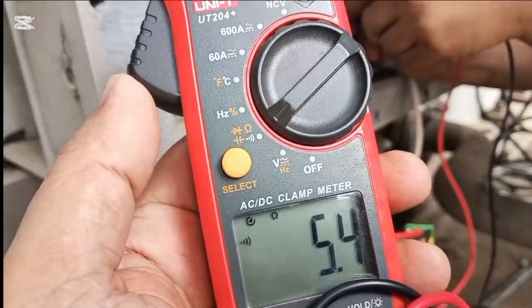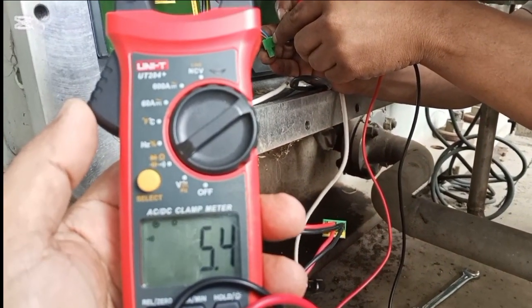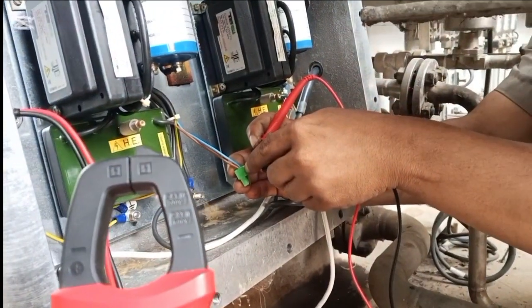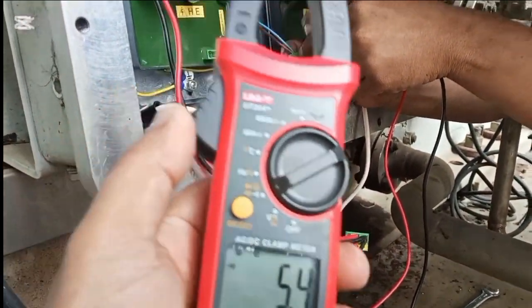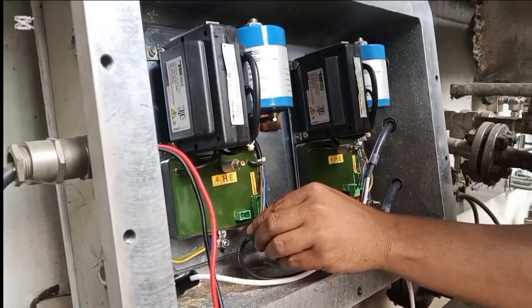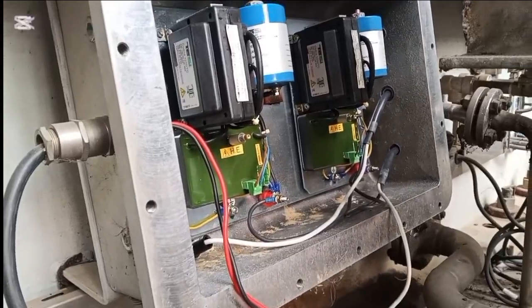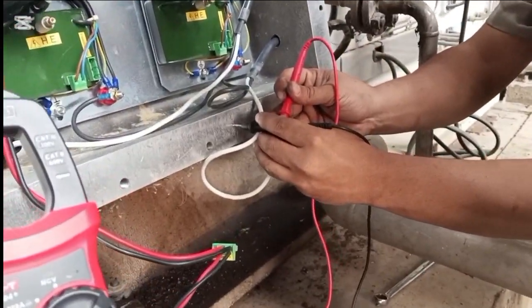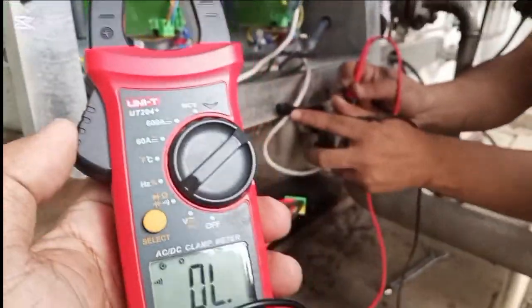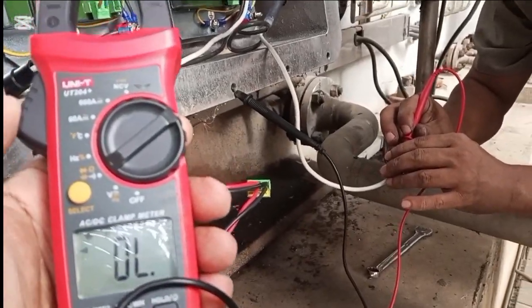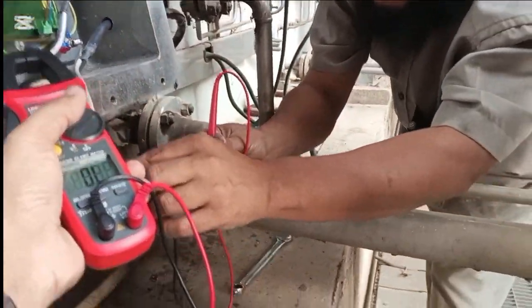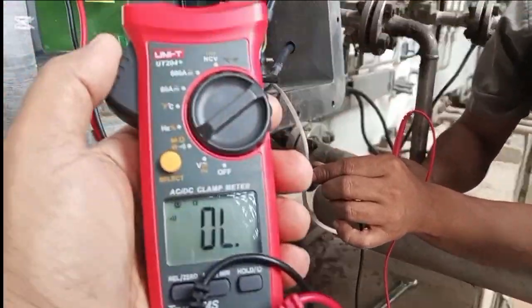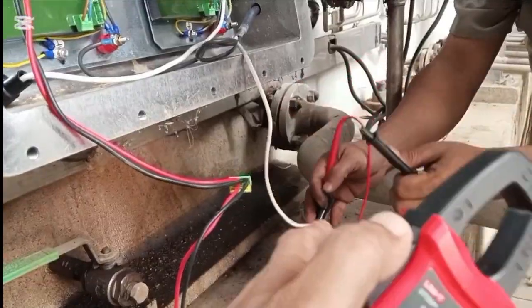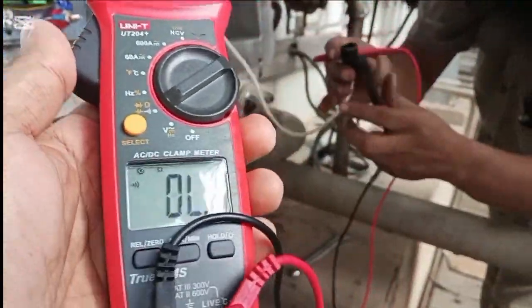Since the ignition was not functioning, we checked the transformer resistance. Here we can see that the transformer internal resistance shows 5.4 ohms, and it is connected with the panel. Another resistance value is from ground to electrode. We found that one is open and another is showing 500 to 600 ohms. This should be some ohms, but its resistance is higher here. One is showing an open condition and another is showing some value.